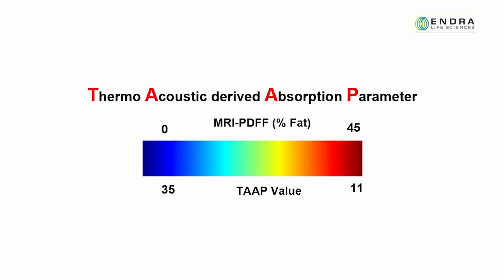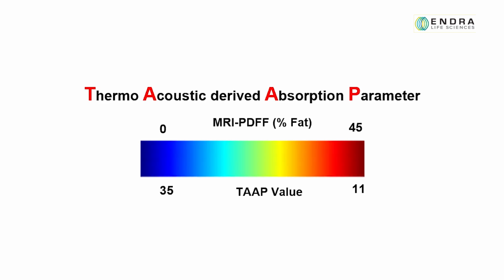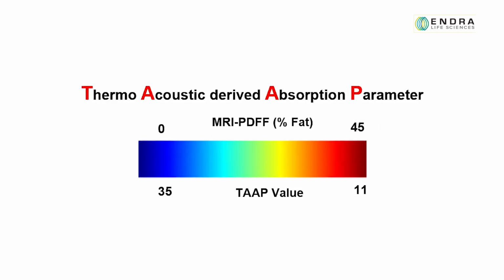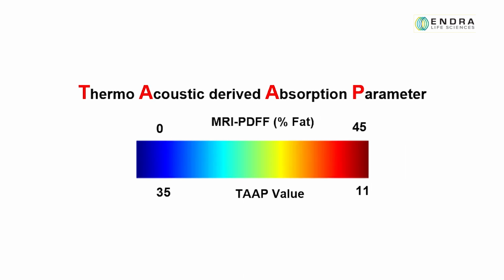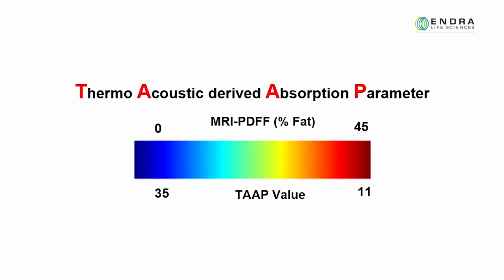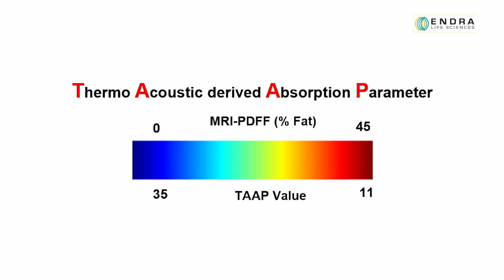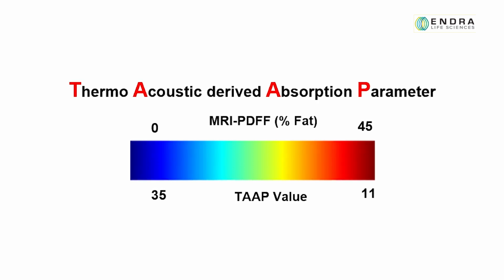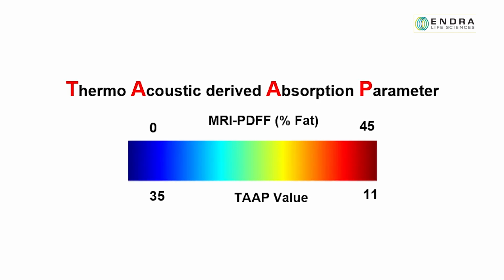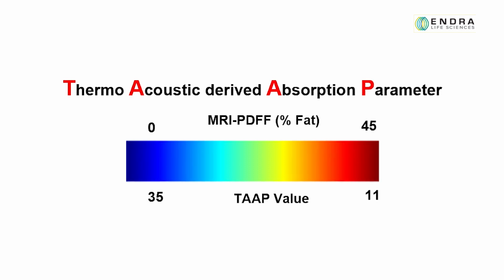Quantitative data, expressed as a thermoacoustic derived absorption parameter, or TAP, are now displayed. The parameter is derived from the two measured thermoacoustic signals and has an inverse correlation with fat fractions determined by quantitative MRI. The lower the TAP value, the greater the degree of fat accumulation.